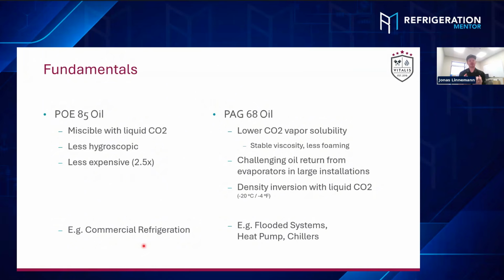Typically we would try to separate the oil with oil drops and stuff. But if you go too low in the temperature of the liquid CO2, it will just start to float up, and then the whole system and the oil recovery doesn't work anymore, right? Yeah, because that oil needs to go back to those compressors. And now if the oil's in the CO2, which is not supposed to go back to the compressors, that's a major issue. I want to talk a little bit about the viscosity too.